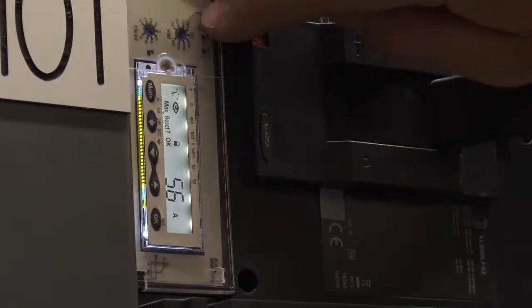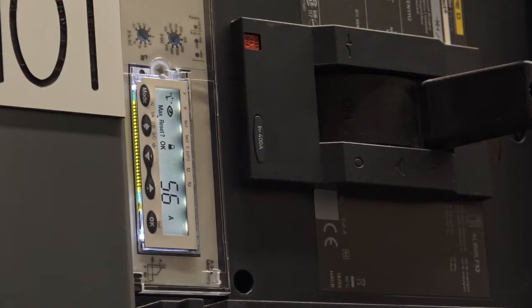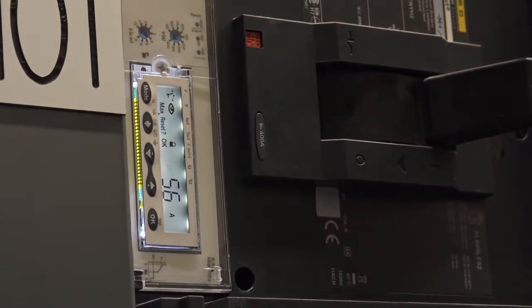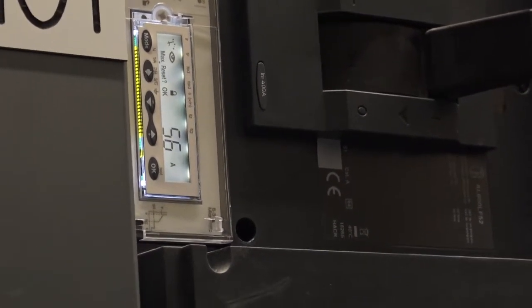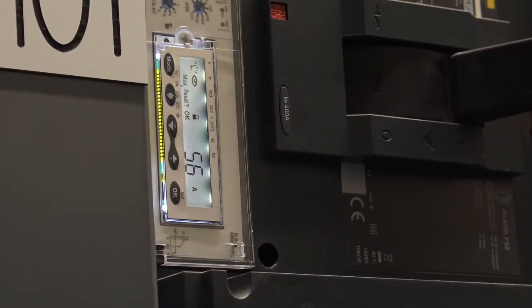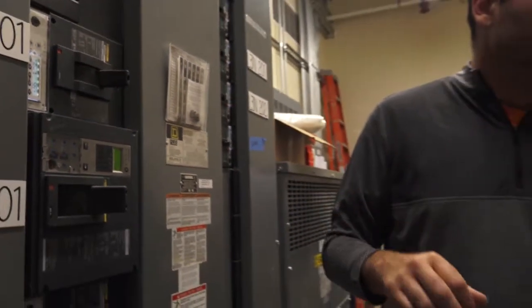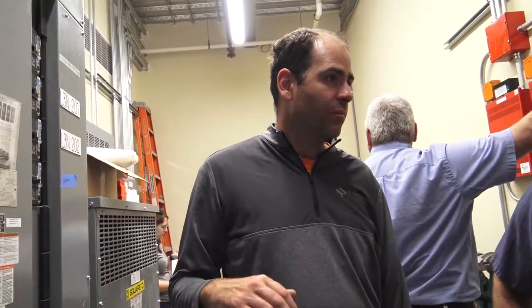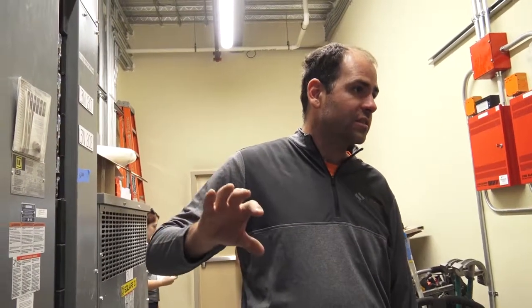We can maybe have Chico run us through all this stuff a little more. He knows more about it than I do. You shouldn't really have to adjust much on these, ever. You should never change the amp setting. If it's tripping, you should probably get a coordination study done and adjust the breakers. Right now the breakers are set basically to the minimum, and they did not opt to get a coordination study, so we could end up paying Square D to come through and set all these breakers. But as of right now, it wasn't in the scope of the work.